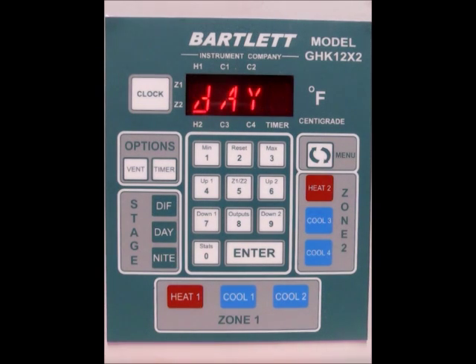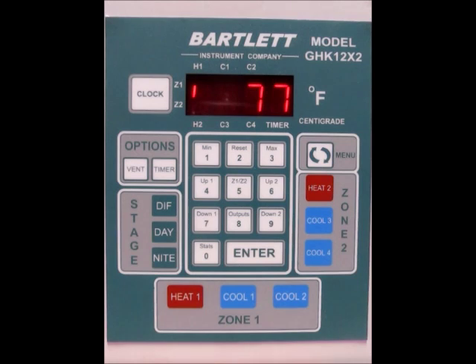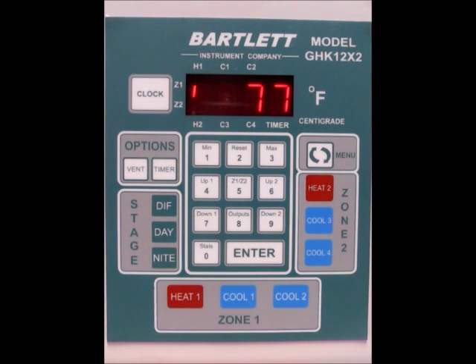Now what happens is that from 5 p.m. until 8:59 a.m., your nighttime temperature of 65 will run. Then at 8:59, it switches over to DIF mode at 70 degrees, and then Day at 9 o'clock is also at 70 degrees — so you've effectively eliminated DIF from the equation. That's it for this one. Remember to like us on Facebook, sign up for our newsletter, or check our website for more information and tips.